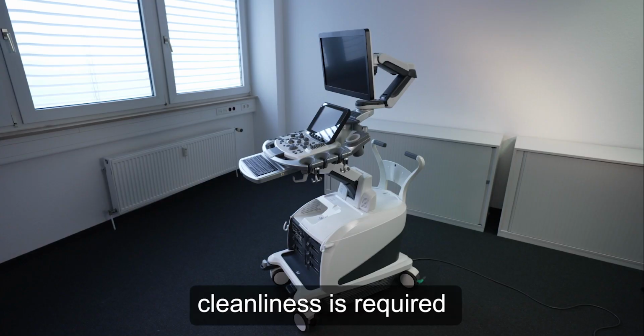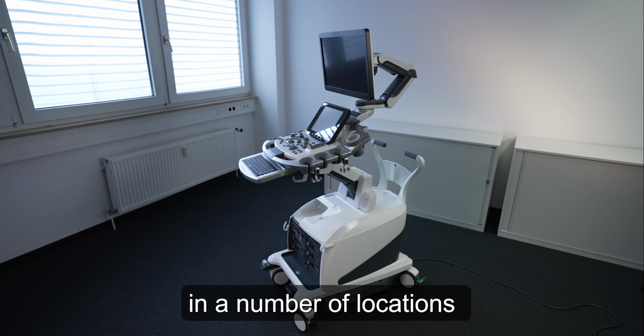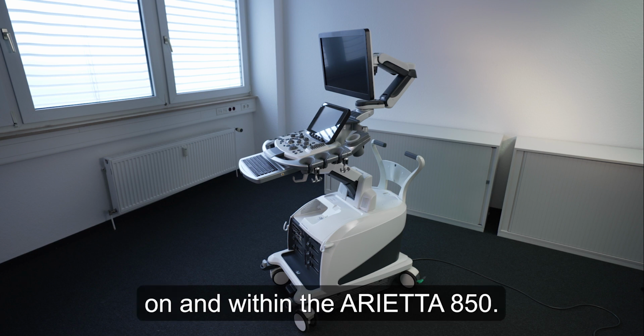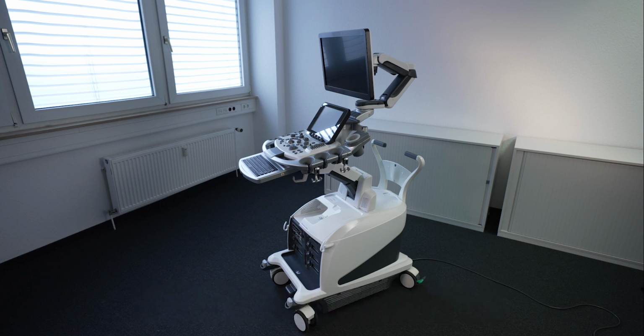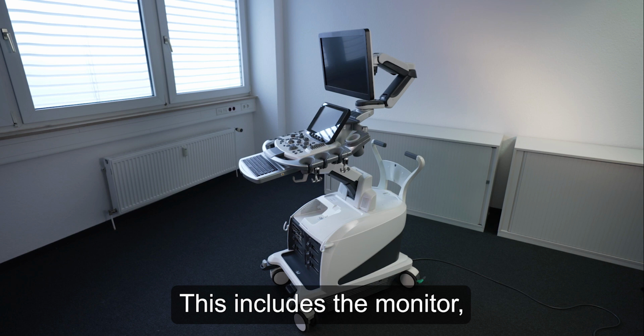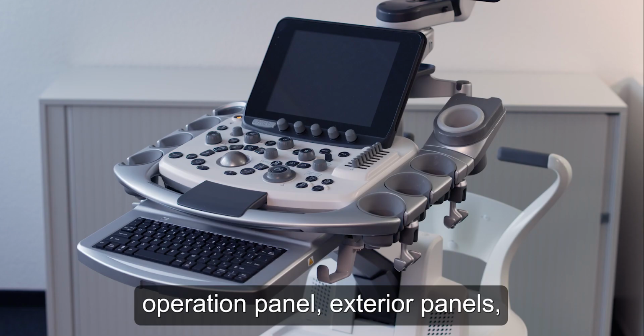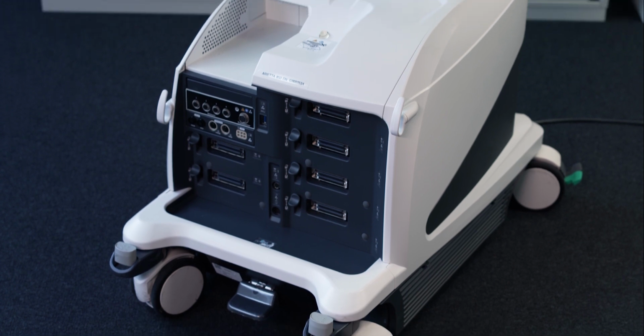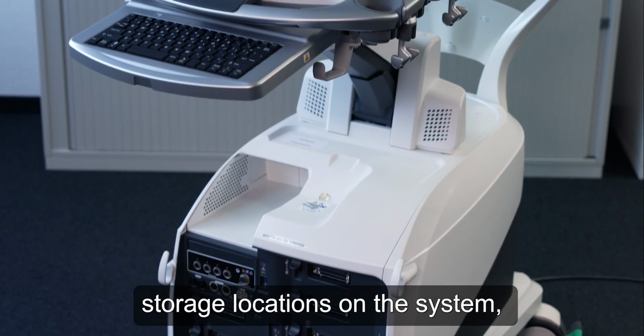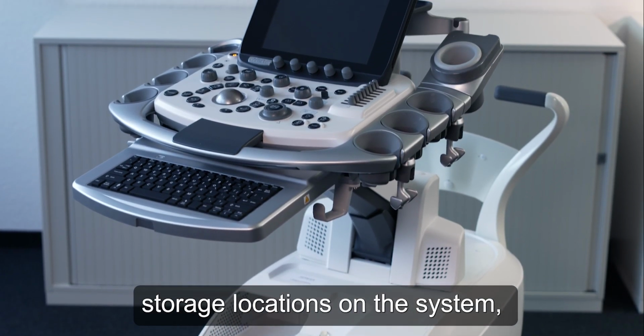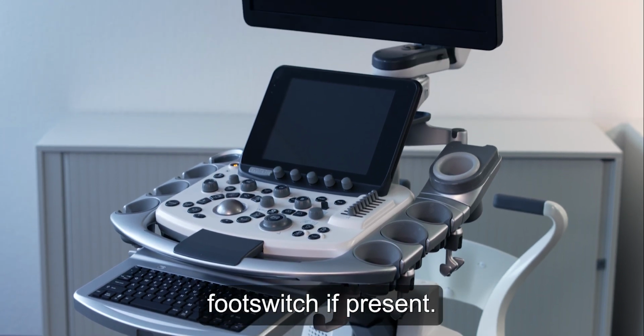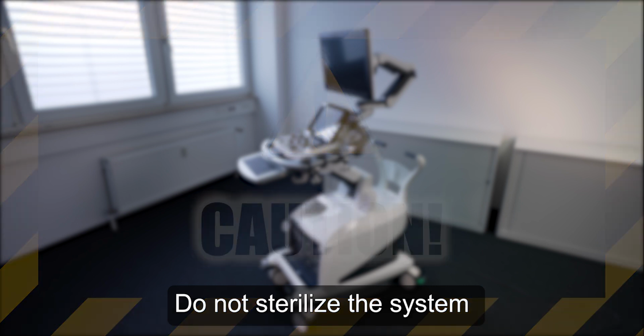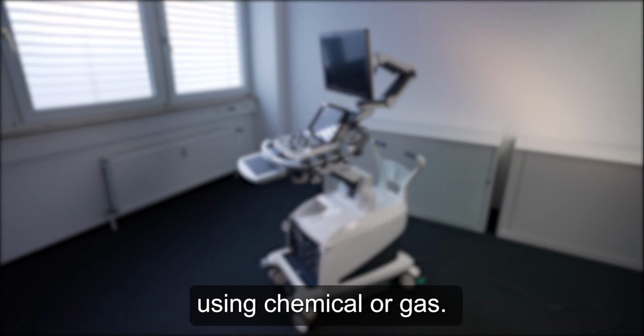An inspection for cleanliness is required in a number of locations on and within the ARIETTA 850. This includes the monitor, operation panel, exterior panels, probe holders, storage locations on the system, filters and foot switch, if present. Caution: do not sterilize the system using chemical or gas. Doing so may damage the system.